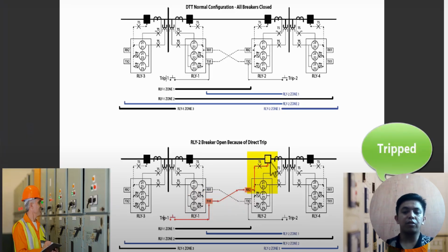There is no reason for you to pull out your fancy GPS test equipment in order to test this scheme. The testing procedure for this scheme is very simple. Put one body at relay 1, another body at relay 2. So get your cell phones and have person 1 push the trip button.